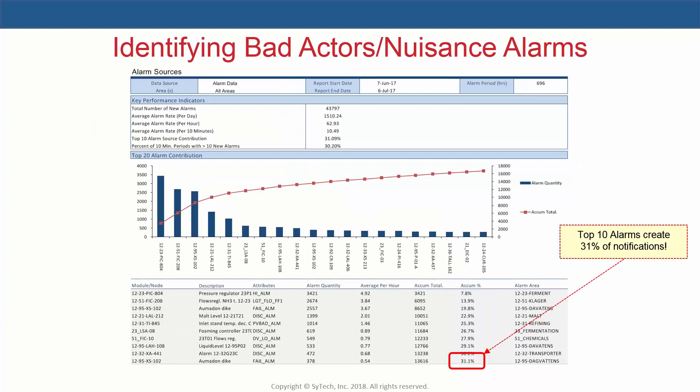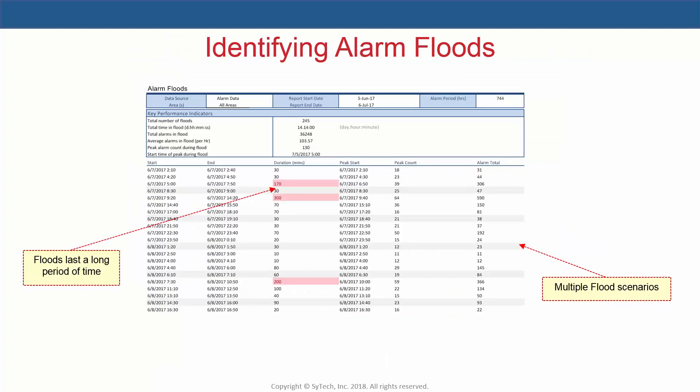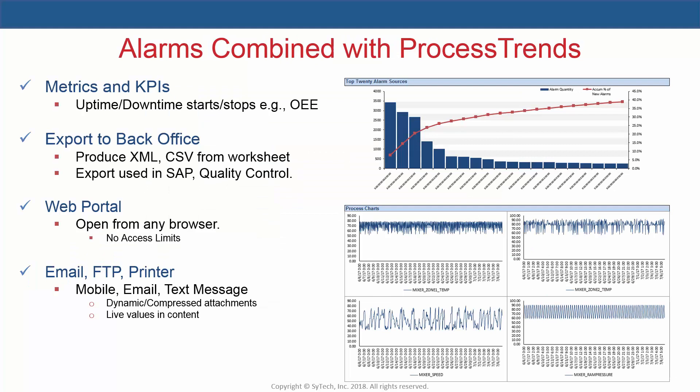The alarm sources report visualizes the top contributing alarms in the system, which can help indicate which alarms are distracting operators the most. The floods report shows periods of high alarm activity, which can indicate when operators are being overwhelmed. Another example shows a custom report where the top 20 alarm sources are combined with data from a process historian.